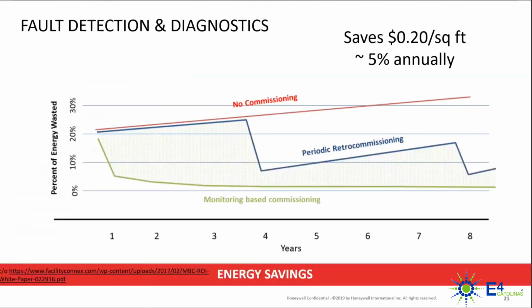Studies show deploying these edge analytics for fault detection and diagnostics saves around 20 cents per square foot, typically about 5% on your annual utility bill. On this chart, everything above the green line is potential energy saved by using fault detection and diagnostic style edge analytics. This is also called monitoring-based commissioning, or in the LEED program, ongoing commissioning - continuously making sure your systems perform to high standards. That's one type of analytics through BMS, driving energy efficiency gains.